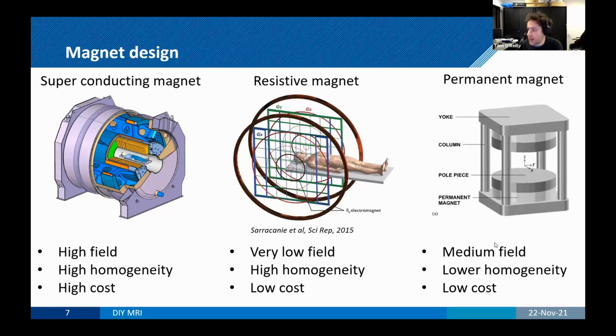Finally, you have the permanent magnets. These will typically have higher field strength than you can get with resistive magnets, especially nowadays with very cheap neodymium iron boron magnets. But they suffer from lower homogeneities - the magnets you buy aren't perfect in their magnetization, and it's much less flexible because you can't easily shape the magnet, or you can, but it's very expensive to shape it into any shape you want. If you use off-the-shelf components, the cost of a permanent magnet system is probably actually lower than a resistive magnet system, because you don't need the electronics.